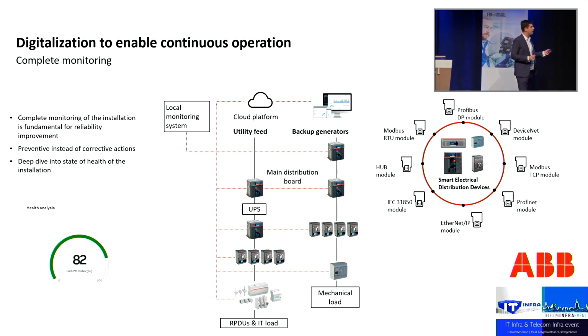So for example, by continuously monitoring data center infrastructure, we can see what is the condition of each and every device. So I need to have devices which are, first of all, capable to measure, to monitor, to communicate. That's fundamental. And then I should have a system which is able to analyze properly this data. Because one device can, for example, even our circuit breaker produces a huge amount of information.